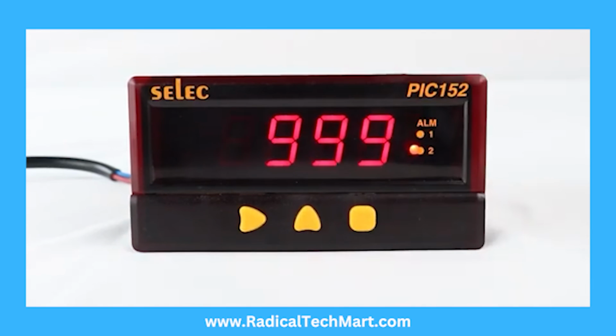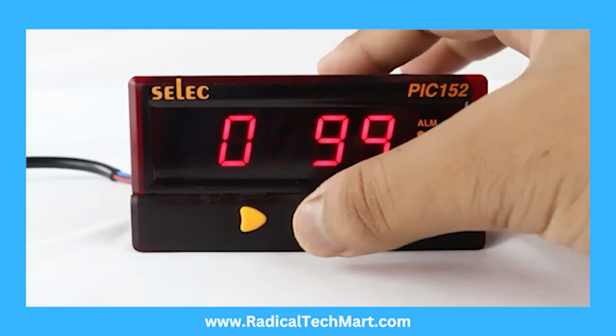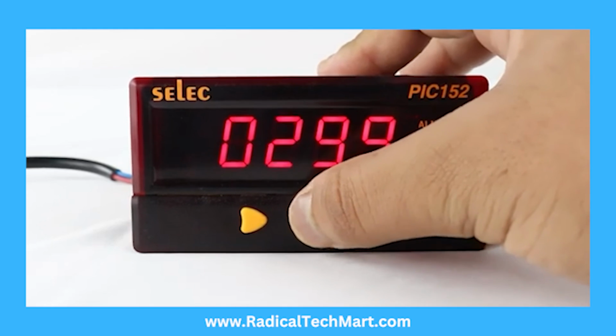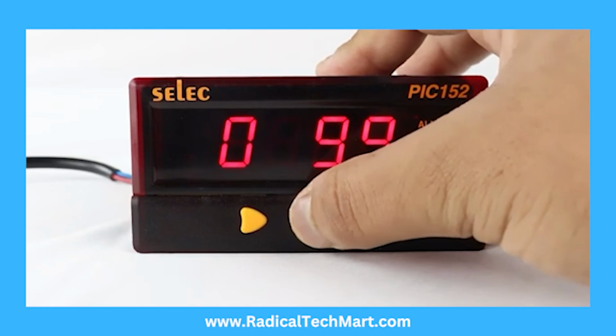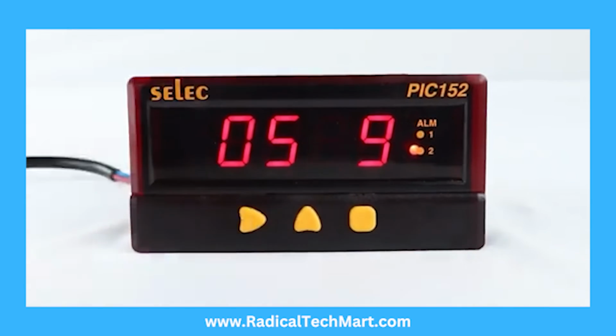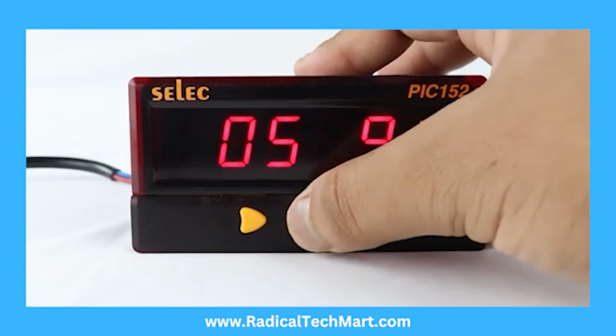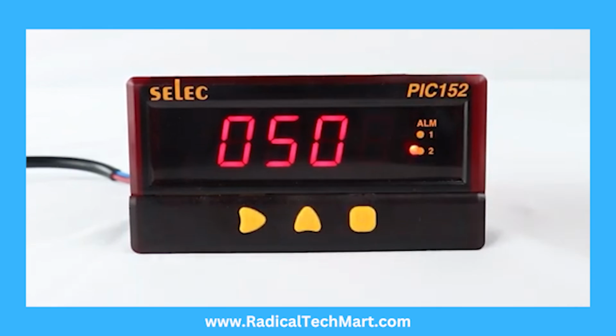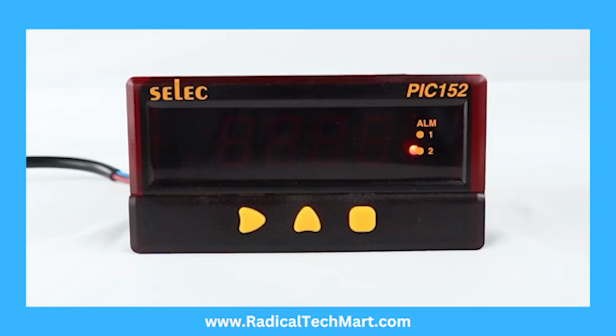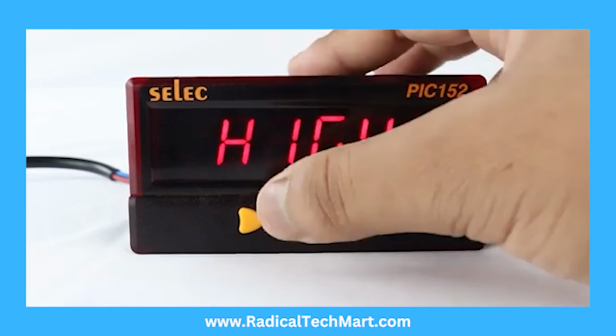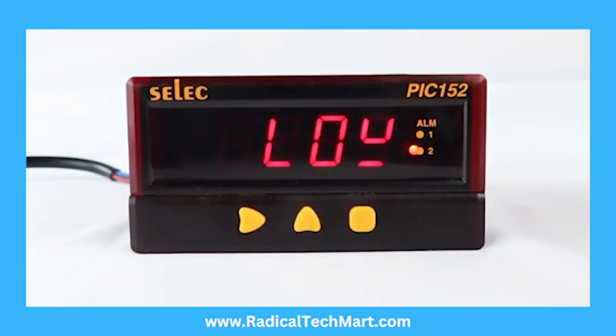Next is analog high scaling point, AHI. For desired output to be 0 mA at 0 degrees Celsius and 20 mA at 500 degrees Celsius, that will be 500. Press the square key to select sensor error level. In case of sensor failure, if selected high, the output will be maximum, and in case of low, output will be minimum.